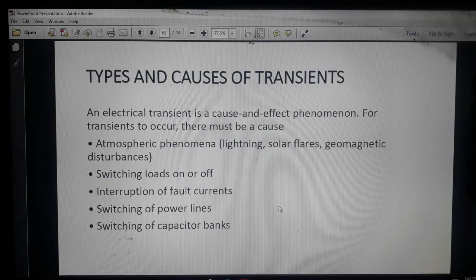Next, interruption of the fault current. Our distribution system covers a large geographical area. Anywhere, due to natural or any other problem, there can be a short circuit between two conductors, maybe line to line, line to ground, double line to ground, or a three line fault, causing interruption of the fault current, and an over voltage transient may be generated. These are the important causes responsible for generating over voltage.